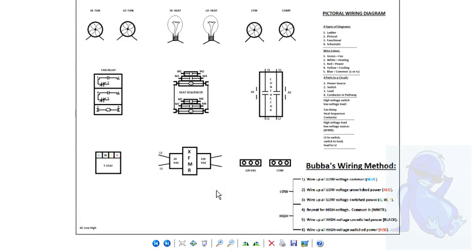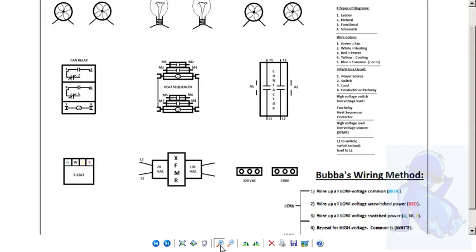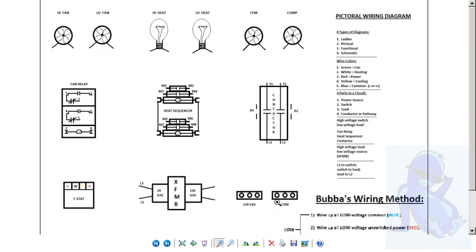Alright, we're wrapping up our pictorial diagrams on the electrical circuit, low voltage and high voltage. So what I want you to do is draw this template out, this pictorial of your L1 and L2, 120 volts in common, a transformer, 120 on one side, 24 coming out here. You got L1 and L2 low voltage circuit. Wire up your thermostat, wire up your fan relay, your heat sequencer, and your contactor in low voltage.